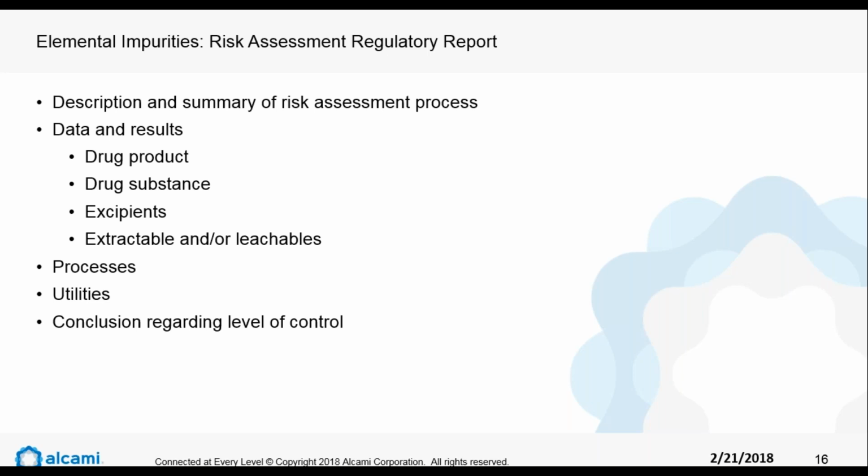As far as the container closure system goes, it's not always necessary to do extractable, leachable studies. That's going to be really dependent upon the form of the drug product. Obviously, parenteral drug products, any type of liquid product, is probably going to need those extractable, leachable studies for elemental impurities. You wouldn't need it for oral solid dose. So that's something we'll speak to in the report as well.